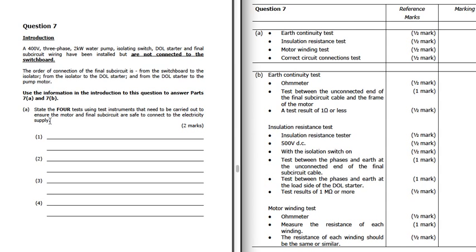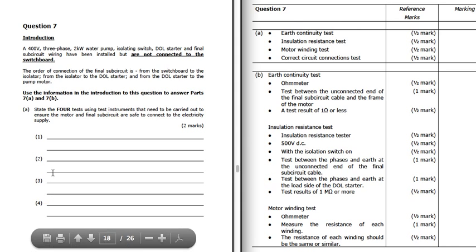So we want to state the 4 tests using test instruments that need to be carried out to ensure the motor and final subcircuit are safe to connect. So with the testing procedure, first test earth continuity, then you're looking at insulation resistance, and then you're looking at testing the motor windings, and then correct circuit connections.